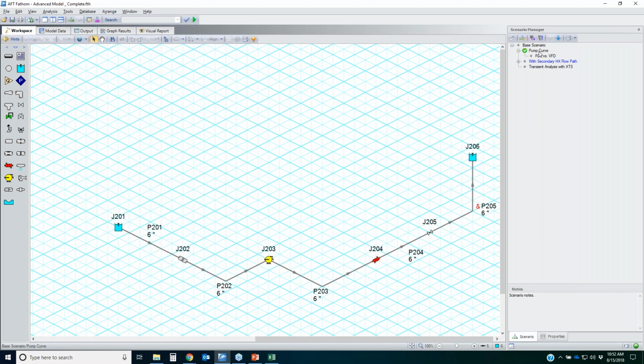Okay, so I have two scenarios. Right now I'm looking at the pump curve scenario. This is a very simple system. I've got a single continuous flow path. I've got a lot of frictional resistance due to a filter and a heat exchanger, which is not a real heat exchanger in this model. That heat exchanger simply represents a whole internal piping system of a plant, and I've just lumped all the losses into that one component as a resistance curve. And then I've got a valve, and then this is a really long pipe right here, and I've got some internal fittings and losses on there.